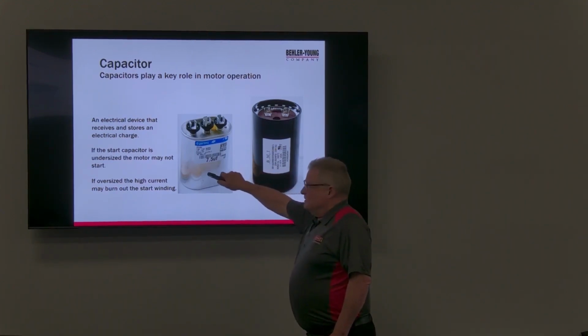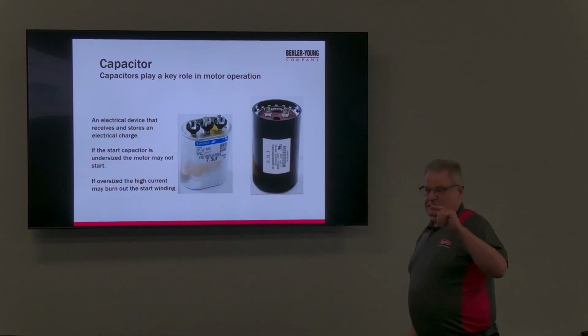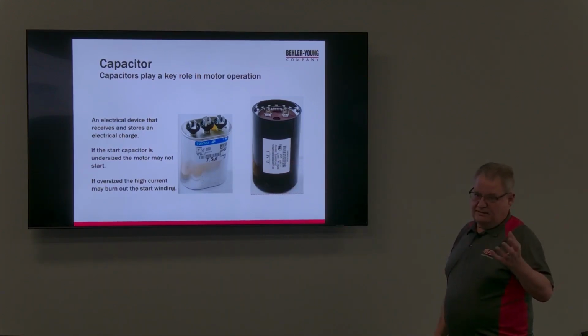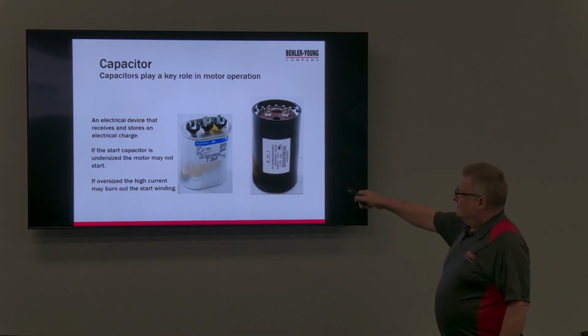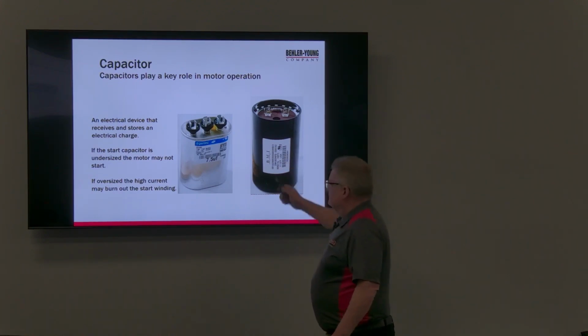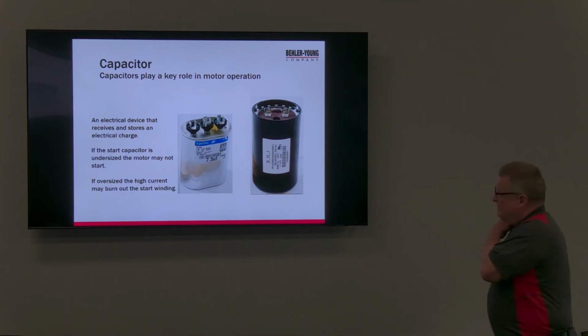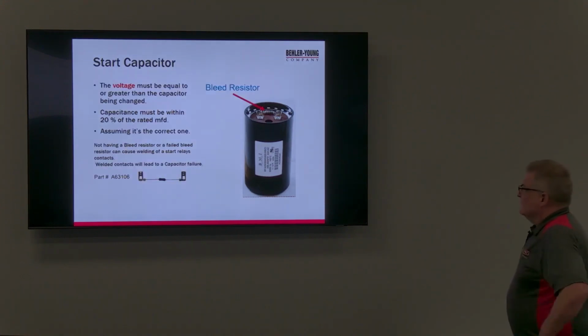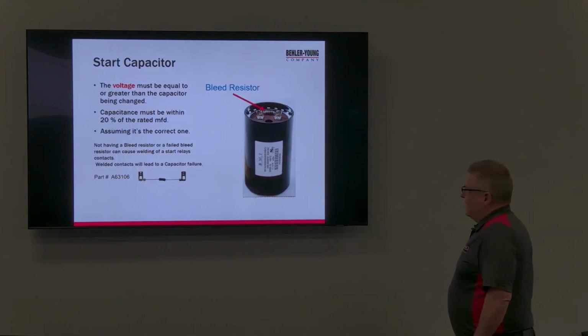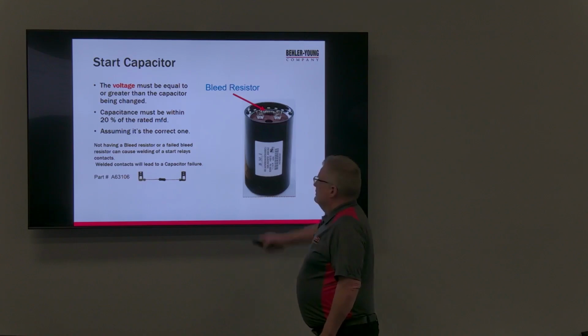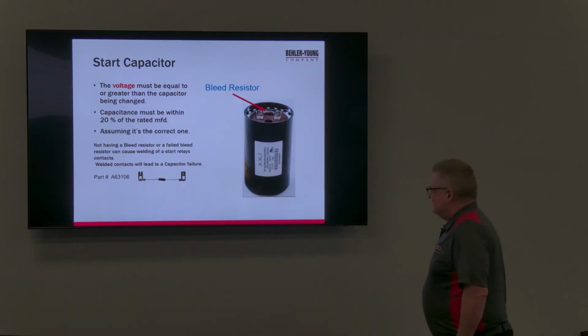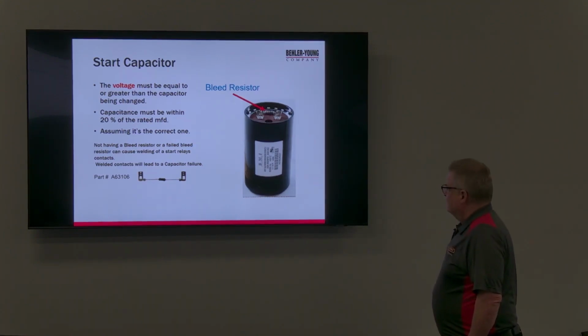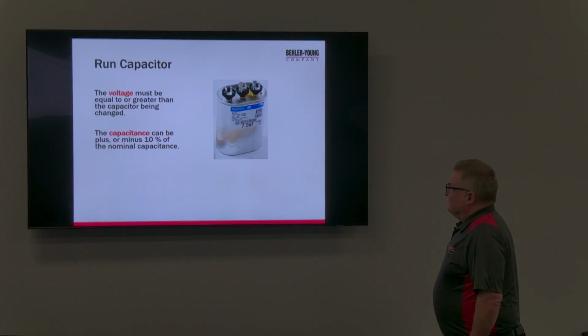The aluminum one is designed to be in the system all the time. It's full of oil, and it stays in the whole time. The start capacitor is only in there momentarily. So again, there's that bleed resistor. If you happen to cut it off because we're going to test the capacitor, we have to cut the resistor off.